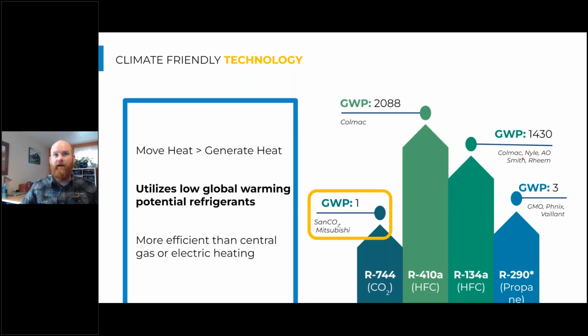And I talked a little bit about refrigerants earlier, but we can look at some refrigerants down here. We have R744, which is CO2. We have R410A and R134A, both fairly toxic, high GWP refrigerants. And then we have R290, propane, which is fairly limited in application right now. And those CO2 refrigerants have a really low global warming potential. This is what the scale is based on. And we have SanCO2 and Mitsubishi with packaged heat pump water heating products specifically targeted towards multifamily building types, as well as other commercial occupancies that are common throughout our built environment.